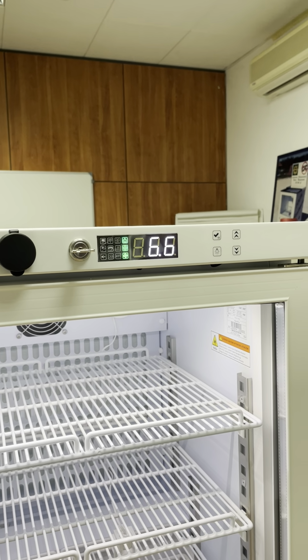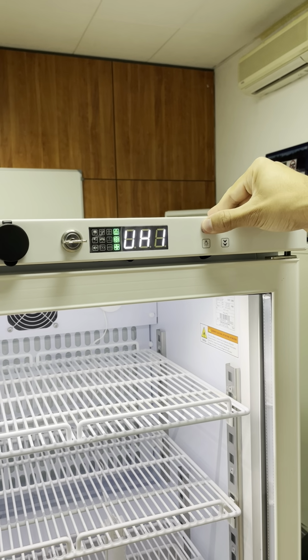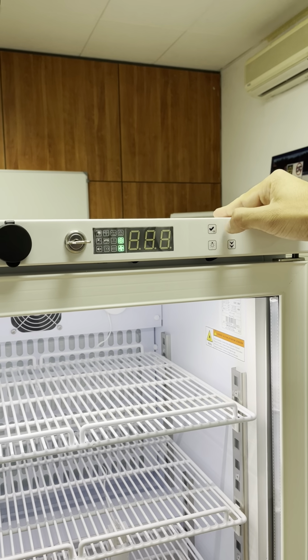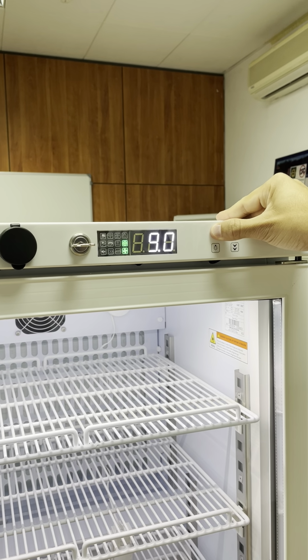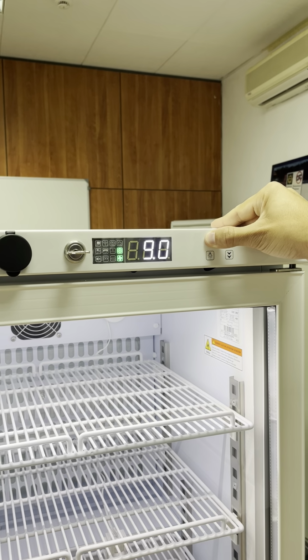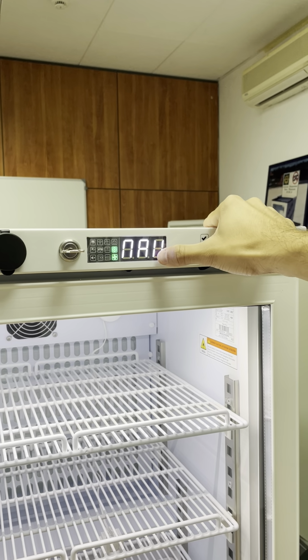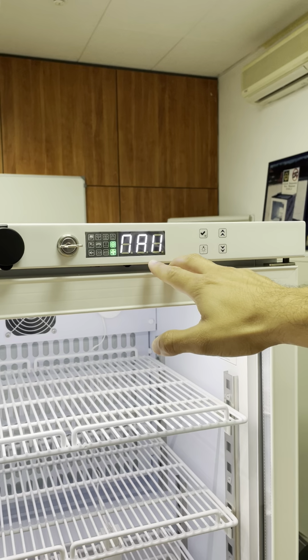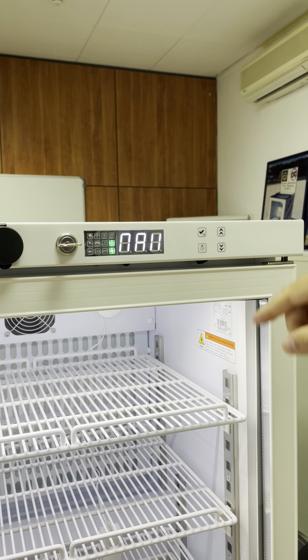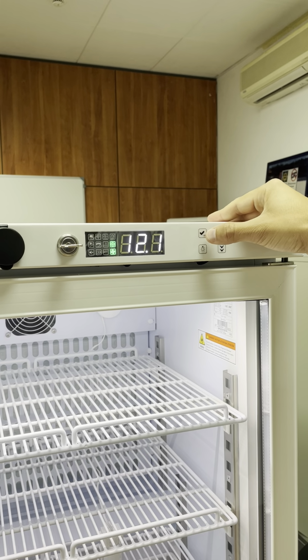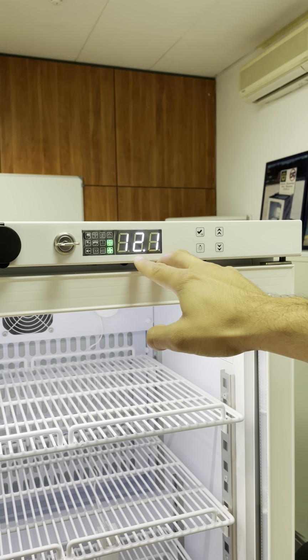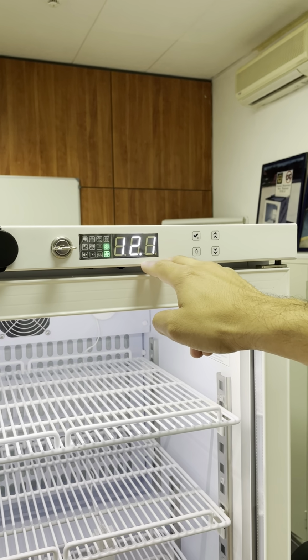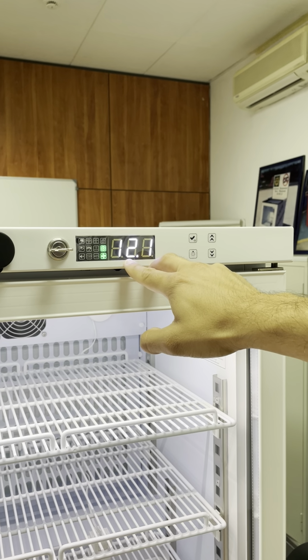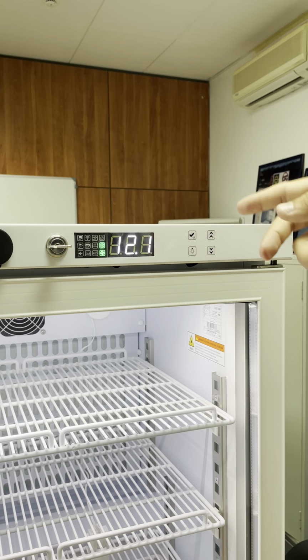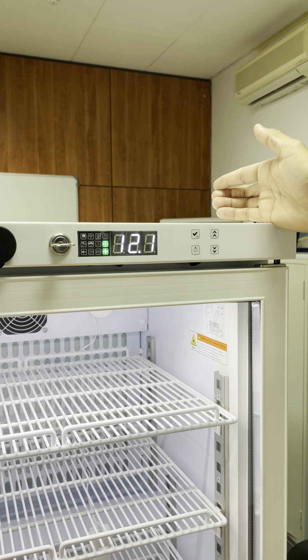To do this, you have a quick way, that is to unblock it and then press on the set, and then you have max. Max means the maximum temperature that occurred in the equipment. If you enter, you see that the equipment went to 12.1 degrees. So this was the temperature that was giving you H1, meaning you had a high temperature on the equipment, and you need to check how it was.